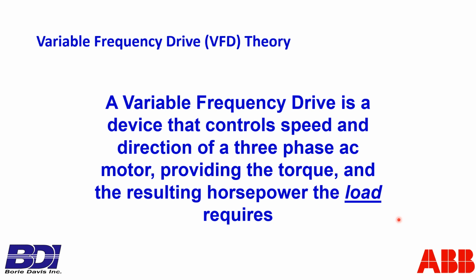If you put a 5-horse drive and a 5-horse motor on a 5-horse load, well, you're doing what's right by design. But if the load increases to 7.5 horsepower or 6 horsepower, that drive and that 5-horse motor are going to provide 6 horsepower worth of torque and power, because they know that's what the load wants right now. That's what the load requires. Well, that's why we put the thermal overload protection in there, because we've got to protect the drive and the motor from overloads, because the drive and the motor are just delivering what the load is demanding.